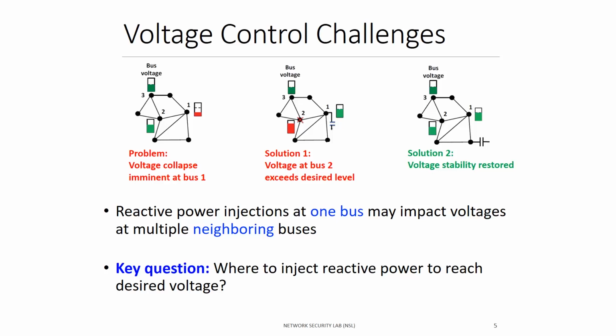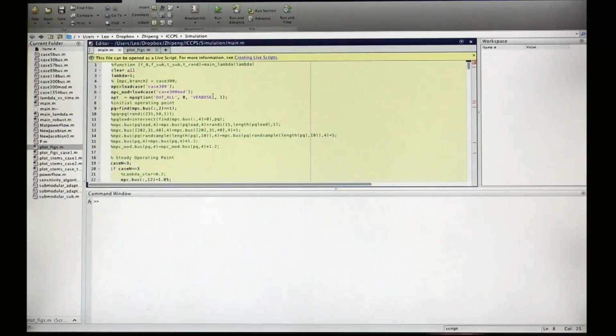So a key question we address in this project is where to inject reactive power to fix the voltage problem when a lot of buses have voltage lower than the lower bound. This demo shows how our method works on the IEEE 300 bus system. It has two important files. The main file generates the states and runs our algorithm. Every operating point is calculated by MATPOWER based on the default data.